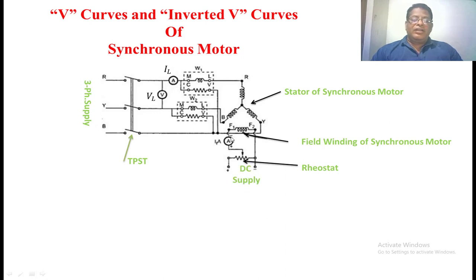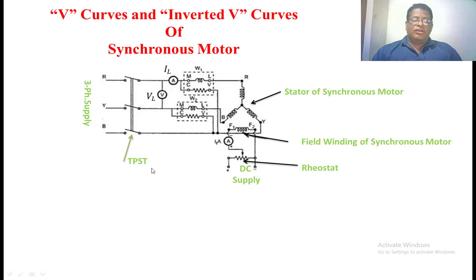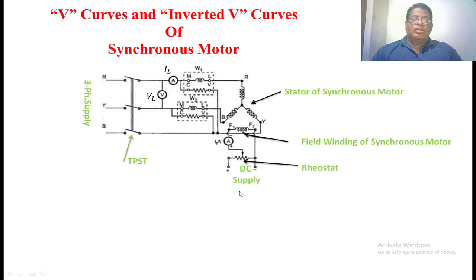Without giving the DC excitation to the rotor of the synchronous motor, first we have to apply the 3-phase supply by closing the TPST switch. The rotating magnetic field is created from the stator winding, and by external means it rotates the rotor in the same direction as the stator flux, near to synchronous speed. Then we give field excitation to the rotor through the potential divider, so the flux created from the rotor synchronizes with the stator flux and the rotor runs at synchronous speed.